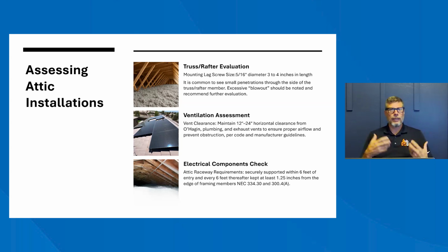Then we've got the electrical components—the raceways, the MC cables, your junction boxes. We want to make sure everything is securely fastened to the truss system where it needs to be, or to whatever they've used to secure it. You do not want anything running loose on the roof deck, or too close to it where it could get damaged during a roof repair, unless it's directly under the panel. If it's directly under the panel, you're pretty much fine there.